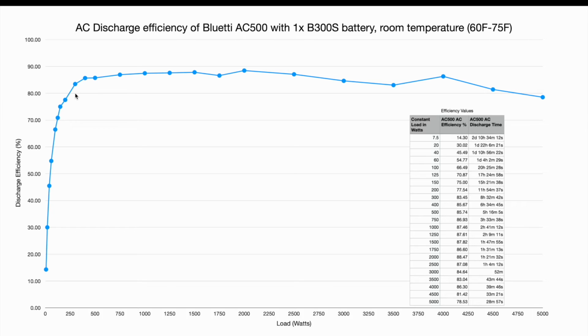You'll also see at the high end of the graph, and this is true on all solar generators, the efficiency starts going back down. Again, completely normal—the cooling has to kick into high gear, and inverters become much less efficient at the very top of their rated capacity. So there's nothing weird about this graph. In fact, I'm kind of impressed with how flat it is, because from 250 watts all the way up to 4,000, 4,500 watts, we're still above 80% efficiency.